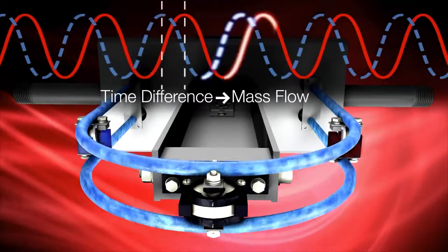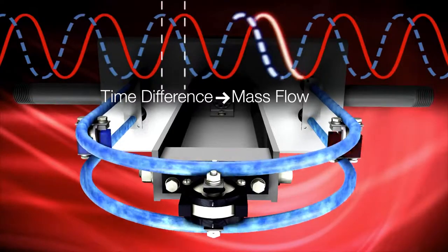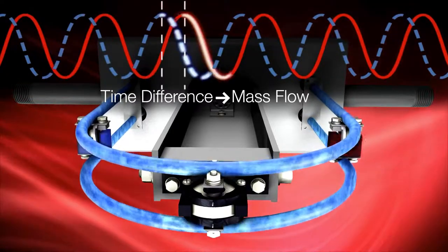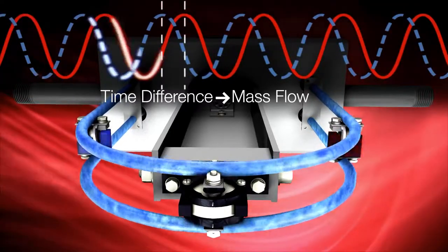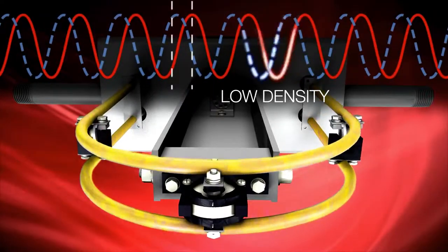The time delay between the two sine waves is directly proportional to mass flow rate. The frequency of the sine waves is also used to measure fluid density. The higher the frequency, the lower the fluid density. The lower the frequency, the higher the density.